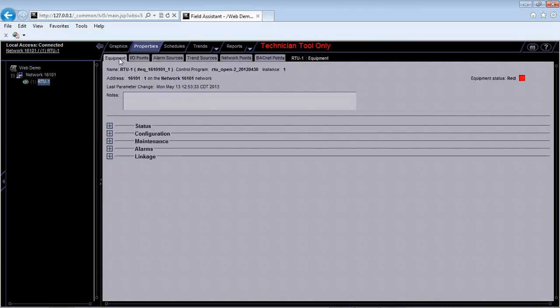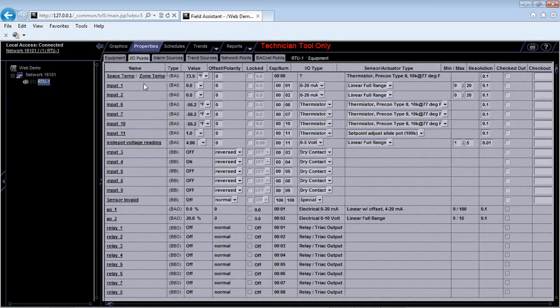I have my equipment tab. I want to click on my I/O points tab. What this stands for is your inputs and outputs physically into the controller. If I click on this, this shows me what my input values are reading for every input. We looked at inputs 1, 2, 3, 4, 5 before. We could adjust those and say what specifically that input is for, but there are specific inputs that are set in stone from the controller. So for instance, input 6 is a supply air temperature and input 7 is an outdoor air temperature. You can check the manual, it'll tell you that, but that's just something I know off the top of my head.